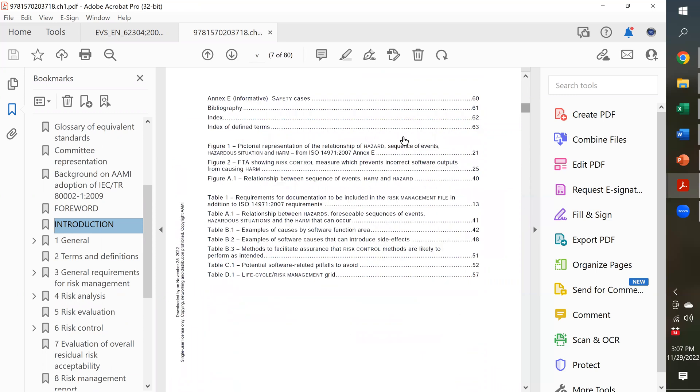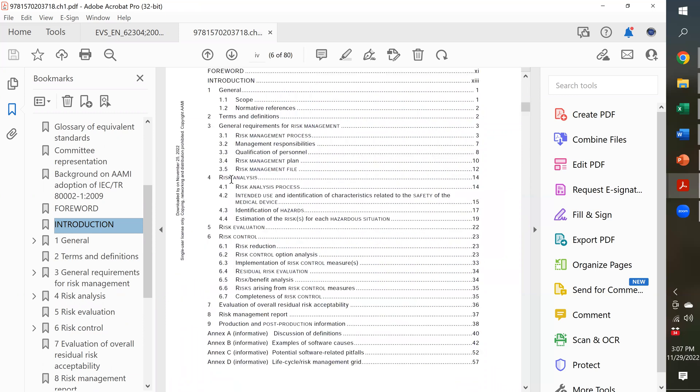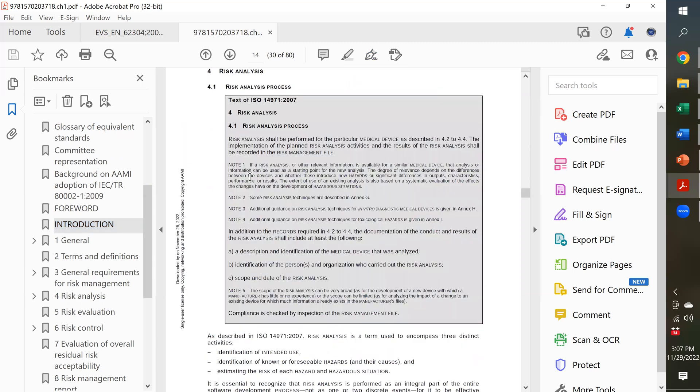So, in the table of contents, they're giving you the different sections of the standard, and they follow along with 14971. So, wherever you had a requirement in 14971, they copied what was in the 2007 version of that standard, and then right below it, they show how they recommend you address that in software documentation for your device.